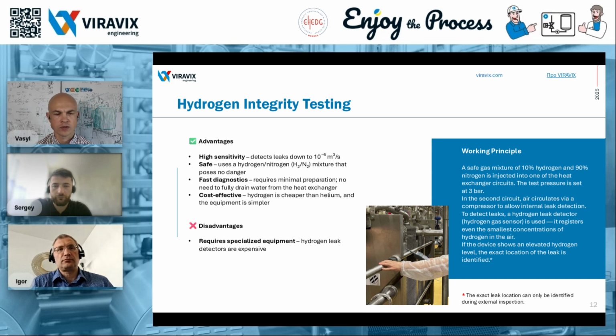Okay. And actually, a question recently came up during a conversation with one of my colleagues in the food industry. When performing a gas leak test, Igor, this one's for you. If a factory performs the test internally, doesn't that create a potential conflict of interest? For example, the technical team might be using equipment that isn't fully sealed, and a test that could reveal that might conflict with their KPIs or internal reporting goals. From the standpoint of test integrity and unbiased results, do you think such testing should always be carried out by an independent third-party contractor, or is it acceptable to keep it in-house? What's your take on that?